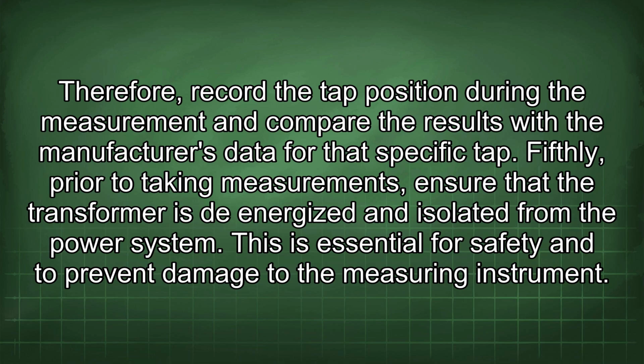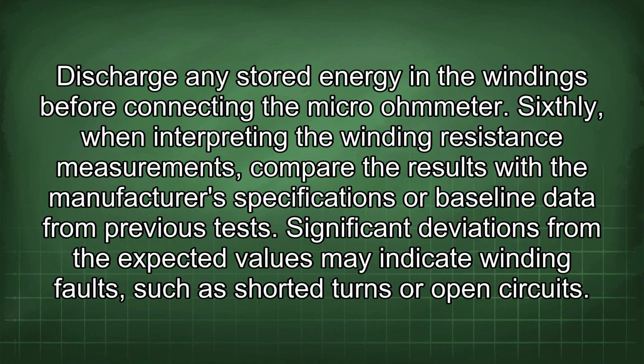Fifthly, prior to taking measurements, ensure that the transformer is de-energized and isolated from the power system. This is essential for safety and to prevent damage to the measuring instrument. Discharge any stored energy in the windings before connecting the microohmmeter.